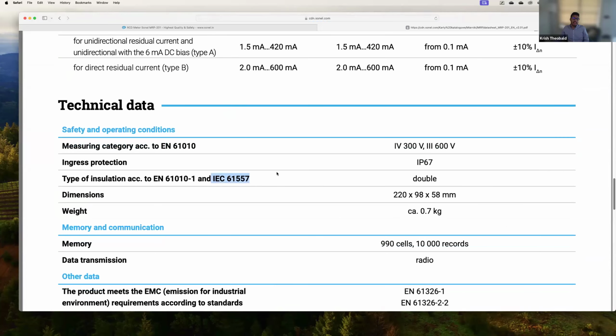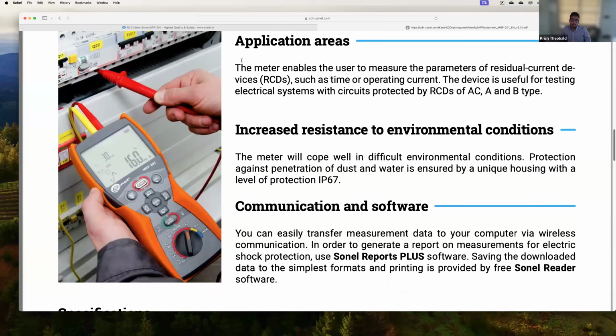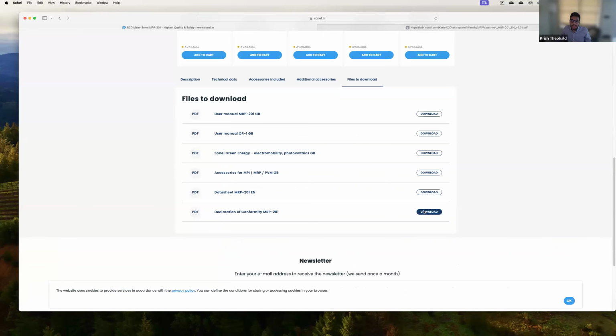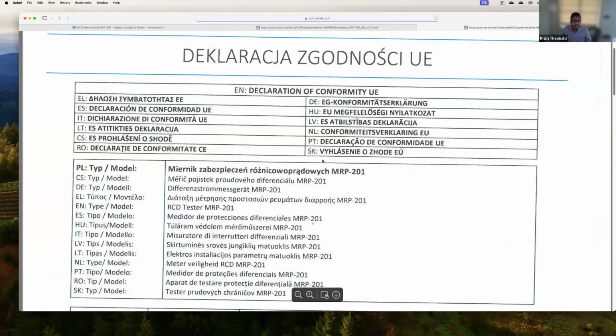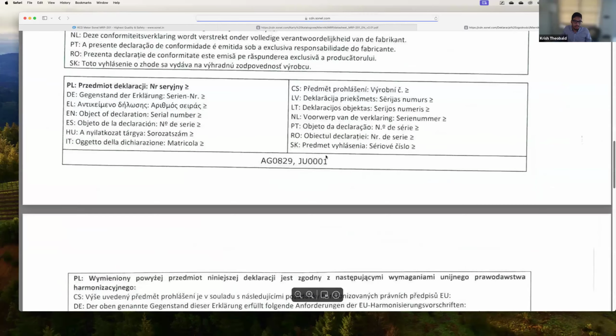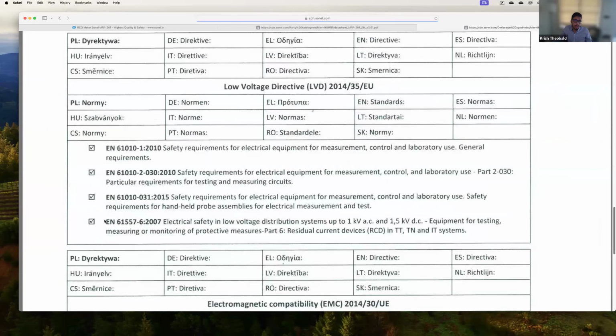61557. So only a device that actually meets the standard can be used to perform the test. If we look at the declaration of conformity, they will have that particular standard written there as well. This is in Polish, so yeah, here, 61557-6. So only an RCD tester that conforms to this particular standard can be used to test. Regarding the first question, Gerard, would you like to answer the second question?